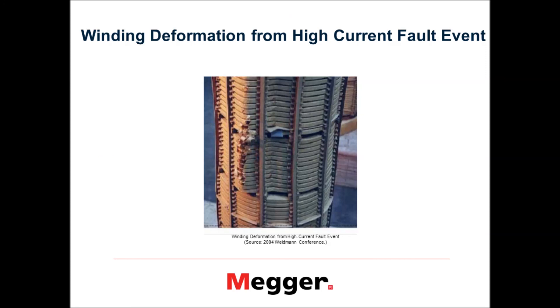This is a very typical example of what a short circuit fault can do to your windings. It can certainly deform your windings and can affect the turn-to-turn insulation as well as the compactness and integrity of the winding.